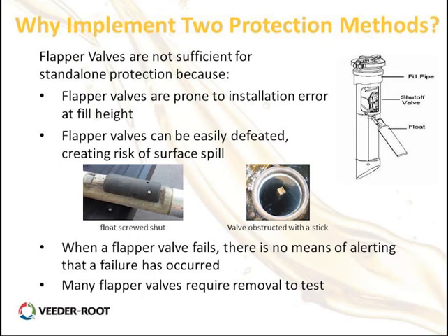Why implement two protection methods? Most people who don't use the Veeder-Root or an ATG for overfill protection feel the flapper valve alone is sufficient. However, installation errors can cause the system not to work properly. The flapper valve can be easily defeated — for example, someone screwed down the shut valve so it would never open, allowing the tank to be filled to 95–100%. When the flapper valve fails, there's no alerting of that failure, and many flapper valves require removal to test.